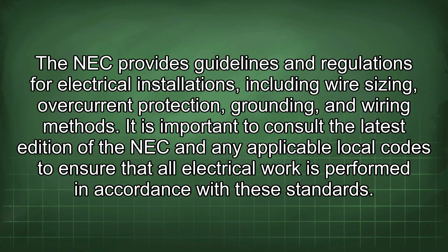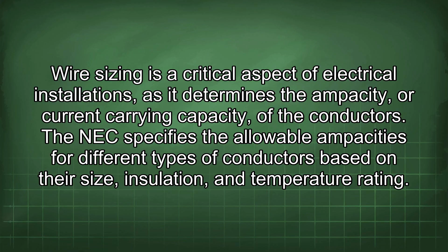Wire sizing is a critical aspect of electrical installations as it determines the ampacity, or current carrying capacity, of the conductors. The NEC specifies the allowable ampacities for different types of conductors based on their size, insulation, and temperature rating. When selecting the appropriate wire size, it is essential to consider the load requirements of the circuit, the ambient temperature, and any derating factors that may apply.